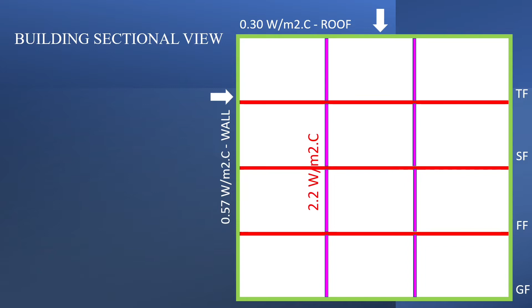Now imagine a situation where the designer makes calculation for the capacity of VRF outdoor units. In addition to the exterior walls, he should consider the wall partition, floor and ceiling partition. The thermal conductivity of partition walls, ceilings and floors is very high, which has a great influence on load calculation. Since one can buy a flat and live in another place, the flat on the side, bottom and top cannot be considered as air conditioned. Sometimes a floor can be empty for a variety of reasons. The designer can never make an excuse that the flat below is empty and cannot achieve cooling.